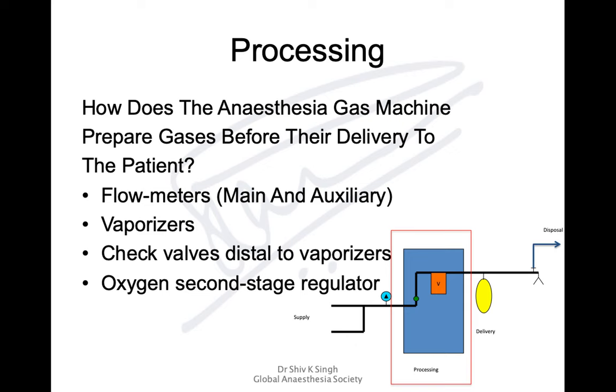Processing is about how the anesthesia machine prepares gases coming in at very high pressure before they are delivered to the patient. This is done through flow meters — main flow meters which we control, or auxiliary flow meters to connect a separate anesthesia circuit or oxygen through venturi devices. Within the machine we have vaporizers to maintain anesthesia, and check valves distal to vaporizers to prevent back pressure.